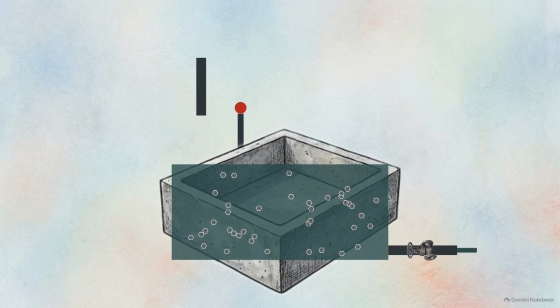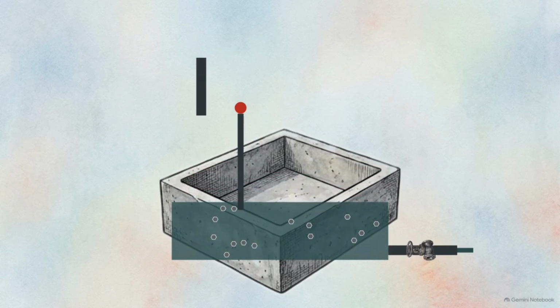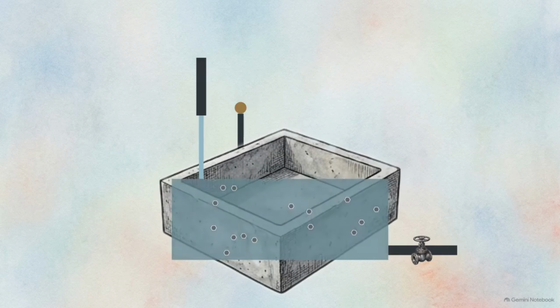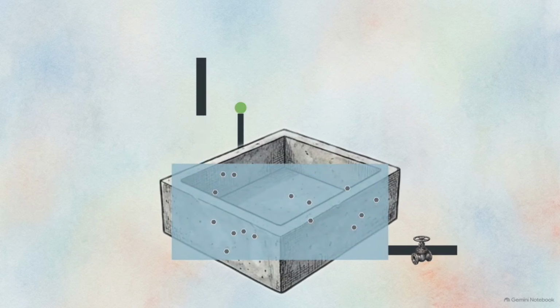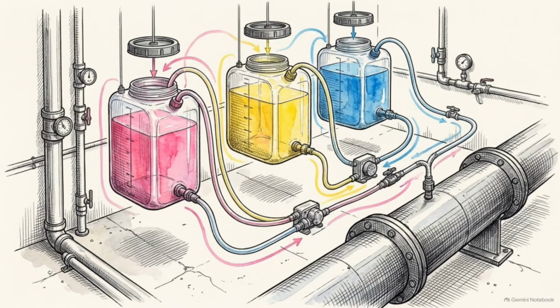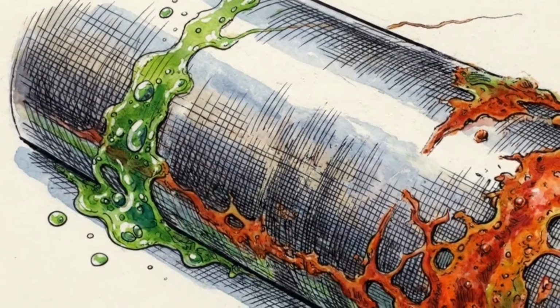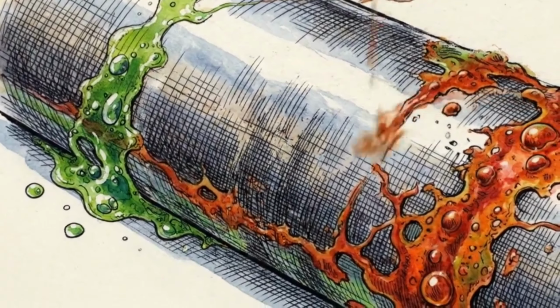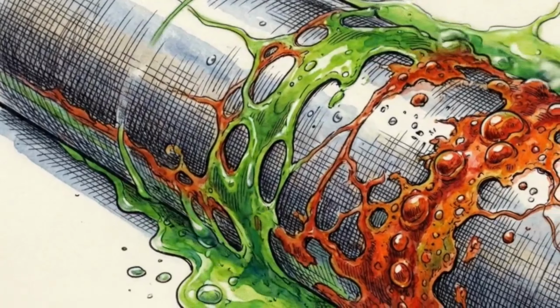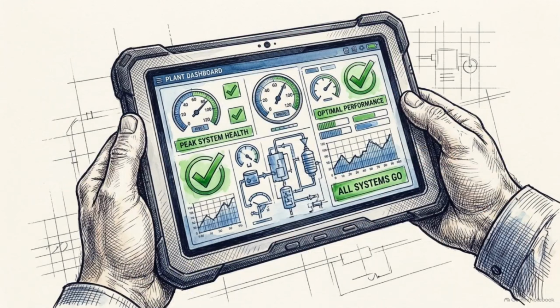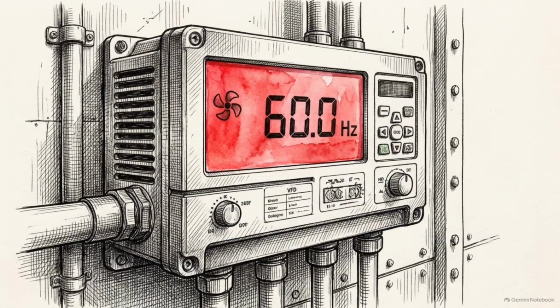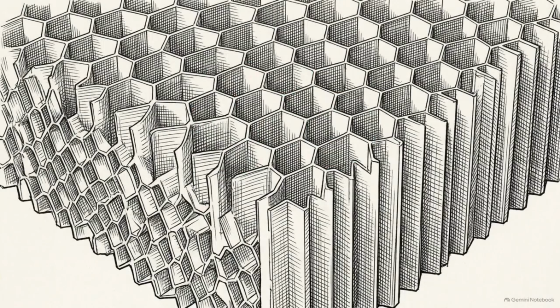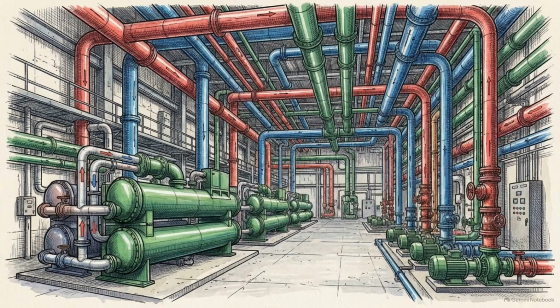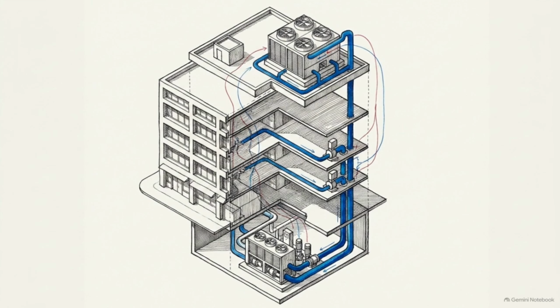When sensors detect high dissolved solids, a valve opens, discharging the heavily mineralized water. Makeup water is then introduced to replace what was lost, safely diluting the basin. Alongside blowdown, the water requires rigorous chemical treatment. Without precise biocides and corrosion inhibitors, the hot, oxygen-rich environment becomes an ideal breeding ground for microbiological growth and rapid metal degradation. Keeping the equipment alive requires operators to maintain variable speed fan optimization, immaculate fill conditions, and strict dissolved solids monitoring. A massive chiller plant operates as a single interconnected organism. The chiller, the condenser pumps, and the water chemistry all rely entirely on the precision and health of the cooling tower to function.